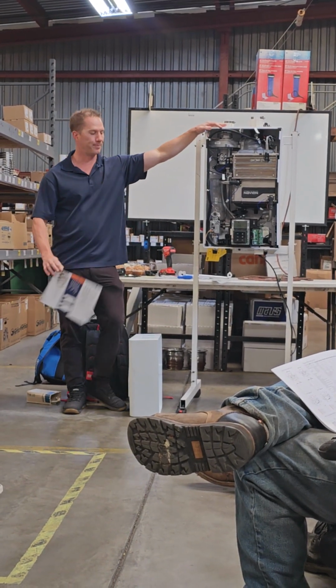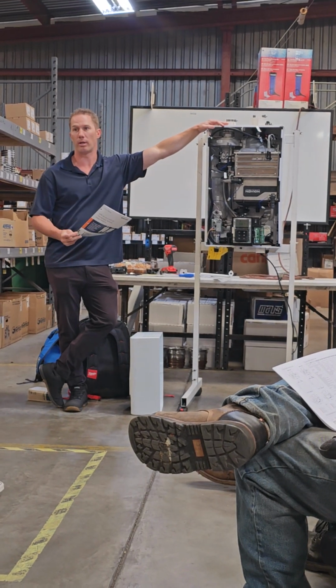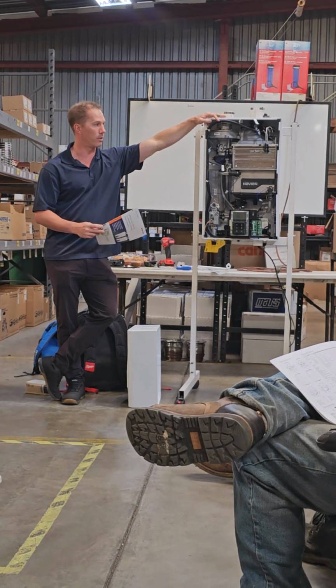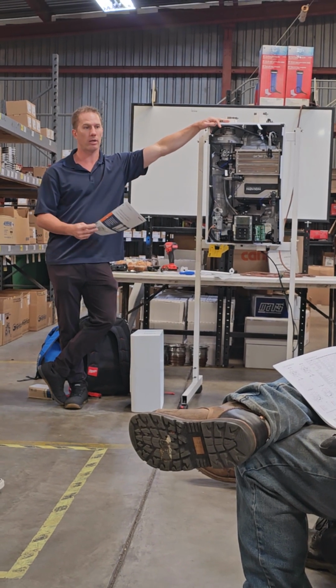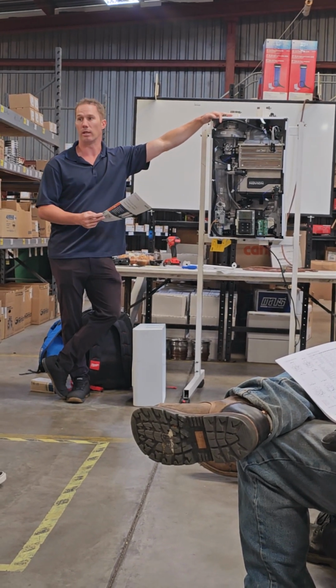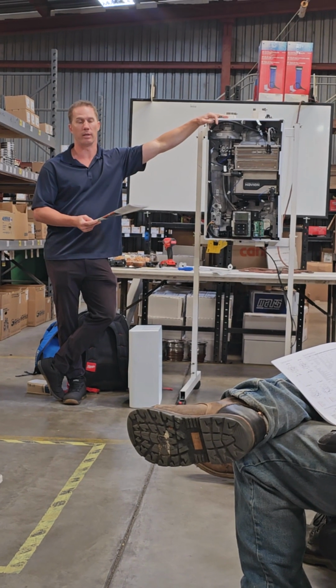But like I was saying, the heat exchanger goes bad because there's hard water. Navien will ask you if there's any water treatment on it. You'll say no, and they'll send you out a new heat exchanger. If the second one goes bad, they're going to say, show me the water treatment, show me what it's doing.